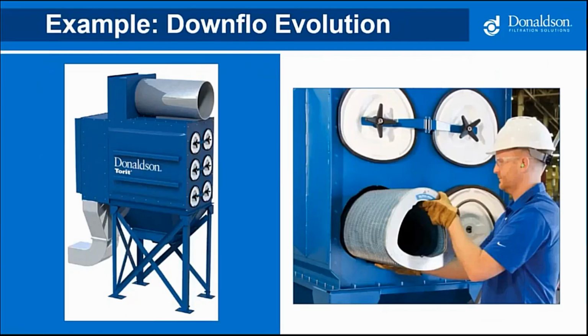Okay, so let's look a little closer at the downflow evolution, and we won't spend a great deal of time. But the DFE, as you can see from this photo, has a very small footprint. We have taken the advice of people over the years, and we've incorporated a lot of things in this. Number one, the filter is triangular in shape. Some people will say buildup on top of the filter. Well, we've minimized this from 25% to 13%. The filters have keyways cut in them right here, as you can see, where there's an asymmetrical yoke that prevents you from putting the filter in backwards.